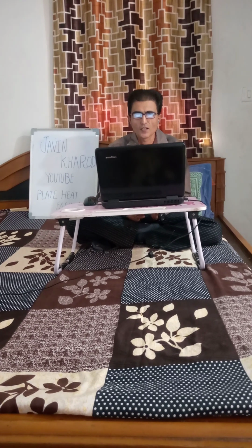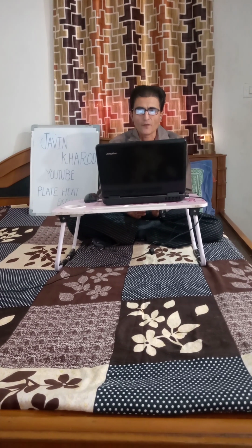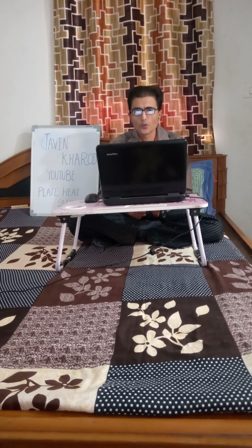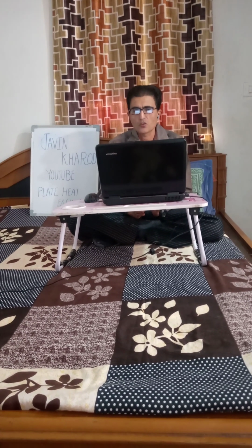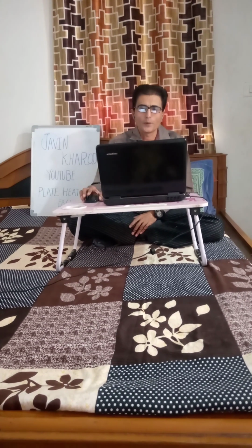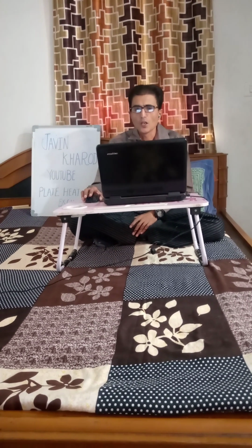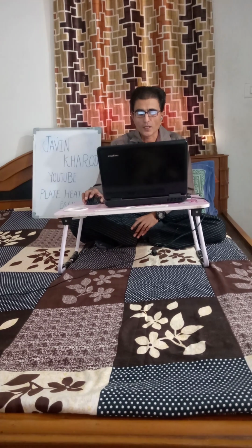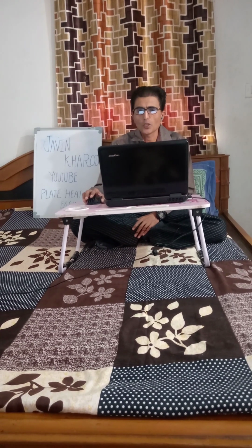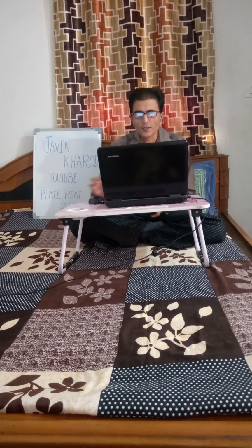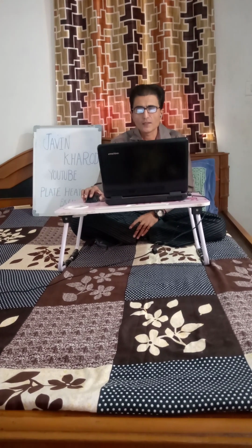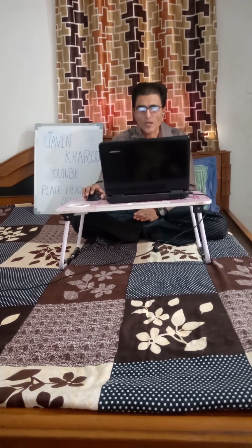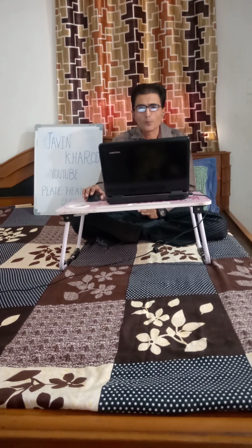Plate heat exchangers are now common, and very small brazed versions are used in the hot water section of millions of combination boilers. The high heat transfer efficiency in such a small physical size has increased the domestic hot water flow rate of combination boilers. The smaller plate heat exchanger has made a great impact on domestic heating and hot water. Larger commercial versions use gaskets between the plates, whereas smaller versions tend to be brazed.